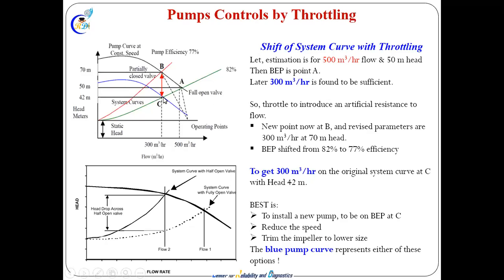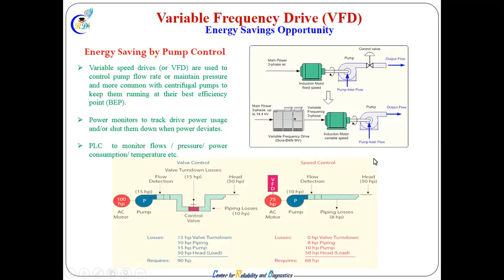If you go to the VFD, at 42 meter head, your head is reduced, which means you are not using more pressure. Maybe your process is satisfied, but more importantly, your flow requirement is satisfied. And the same thing is explained here. You can see 100 HP with valve control, 15 HP lost, which is zero here.